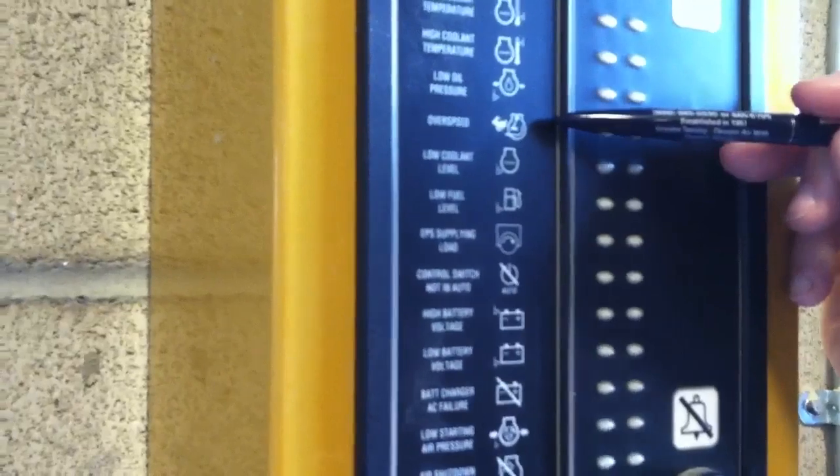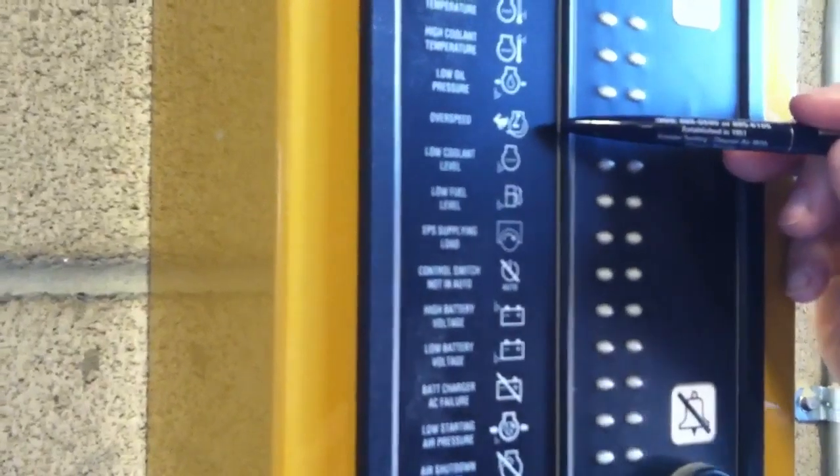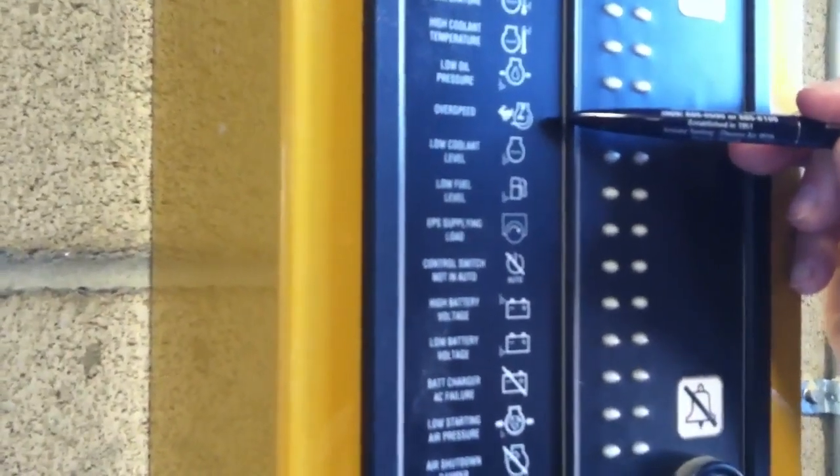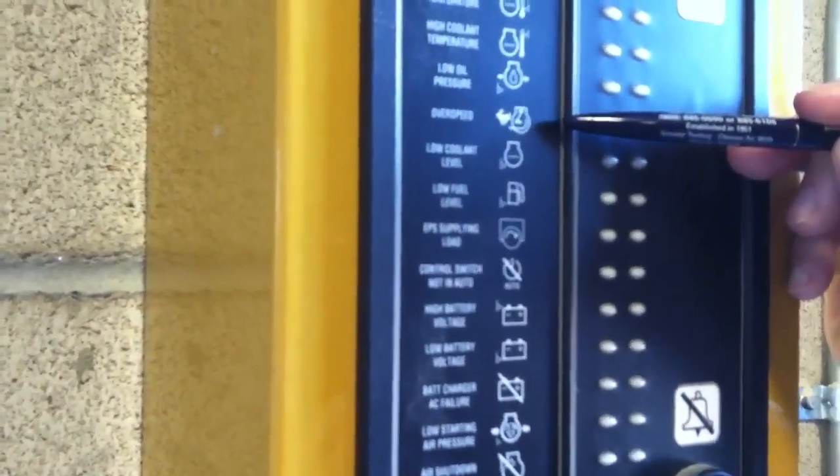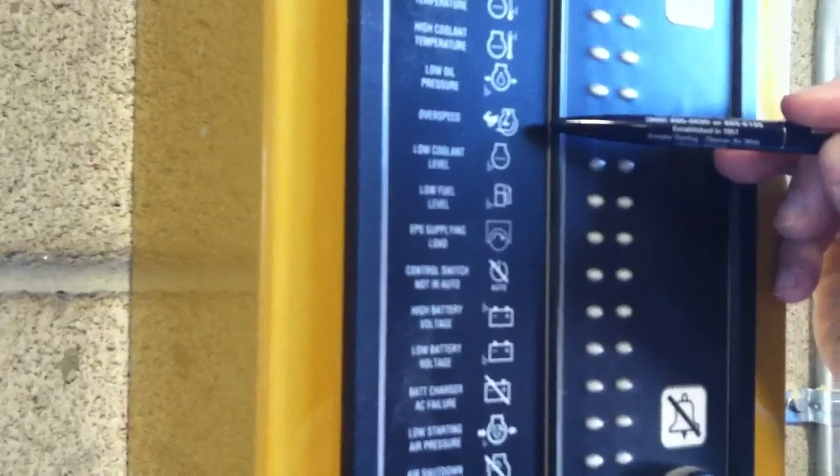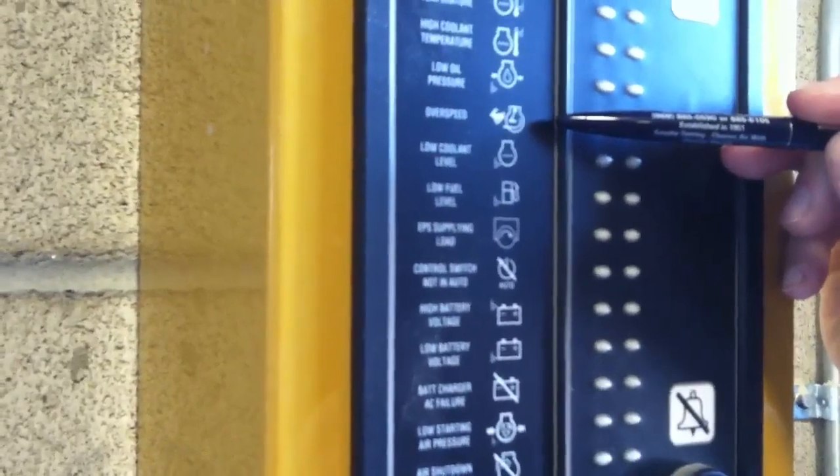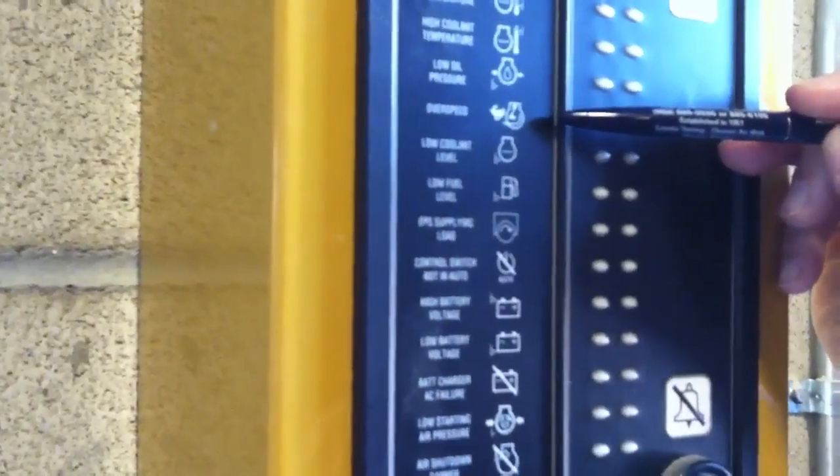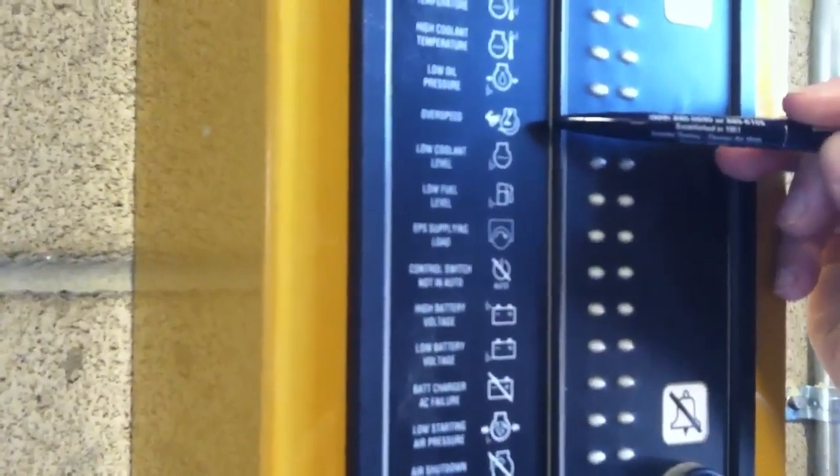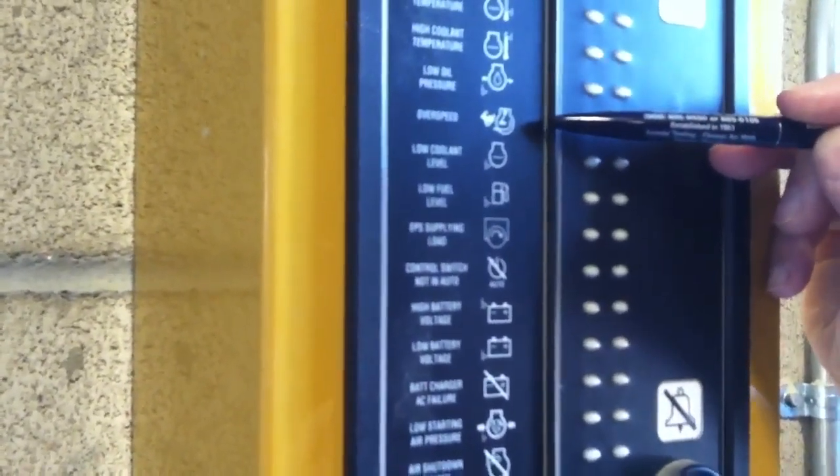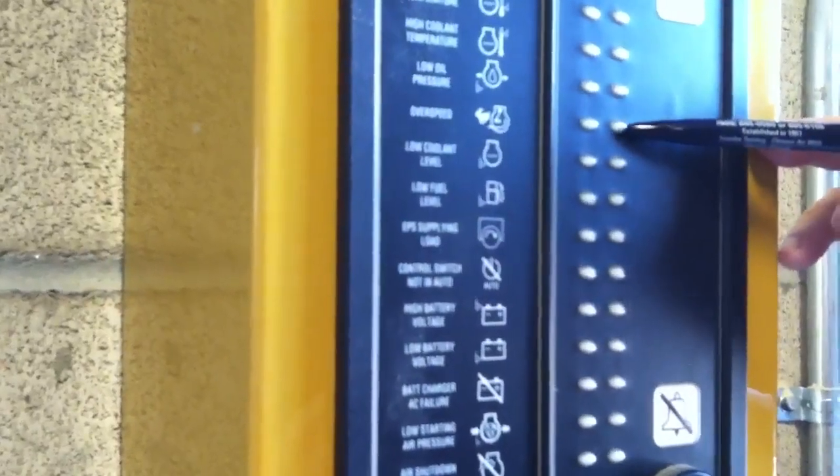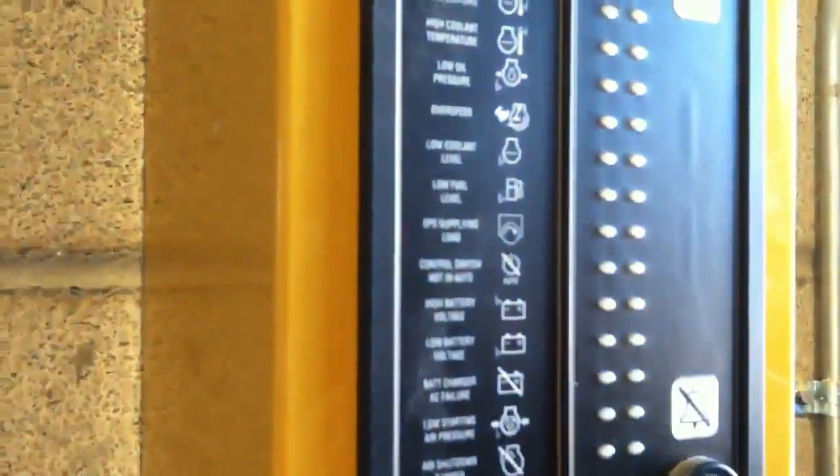Overspeed, again the engine runs at 1800 RPM and if we go to 2120 RPMs which would mean we don't have governor control anymore we're going to have a shutdown for over speed.